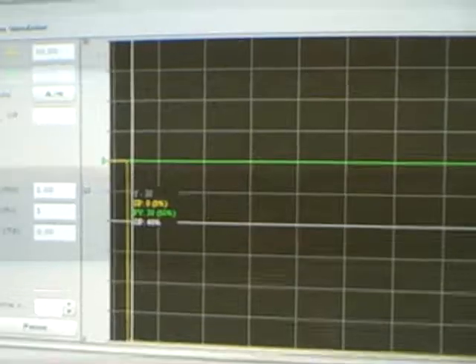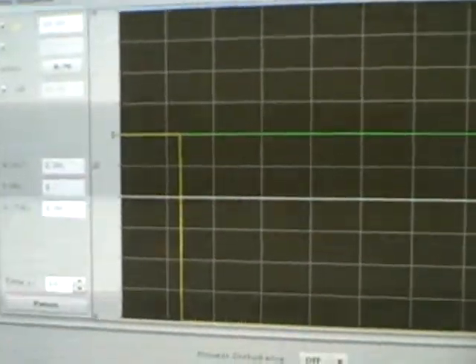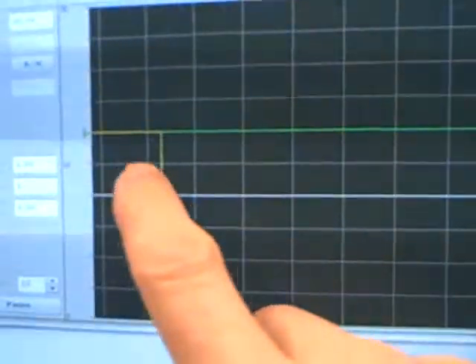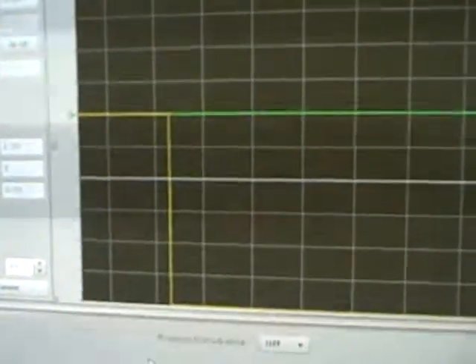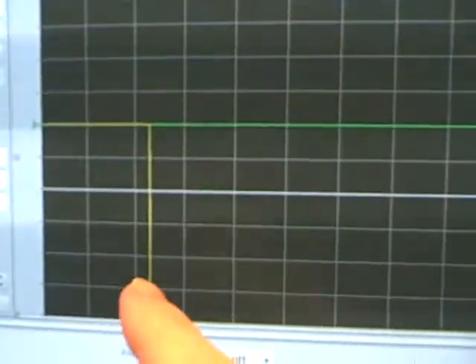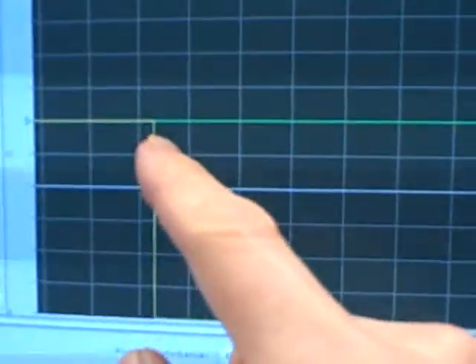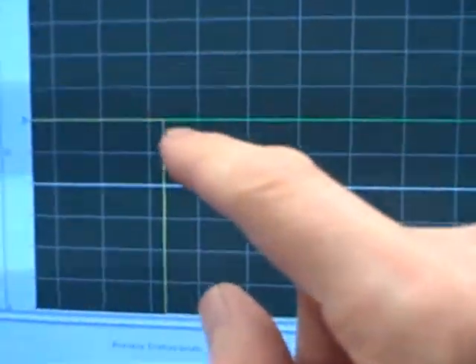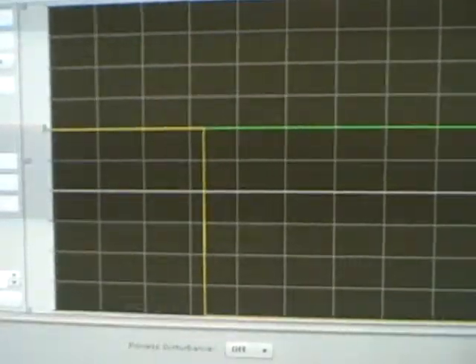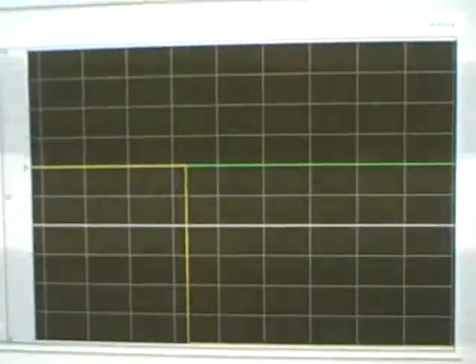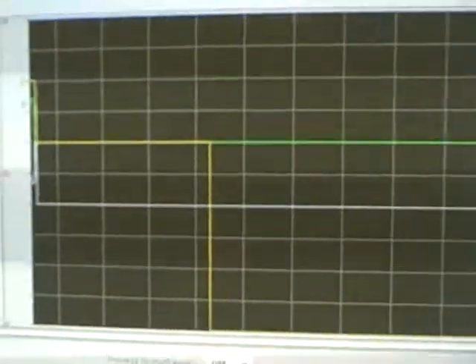I'll switch the controller into automatic mode. Now, the controller is actually going to take action if it sees an error develop between process variable and set point. When I made the change to automatic mode, we see the set point value in yellow jump up right here. Basically, it went through the set point tracking feature. When we came out of manual mode into automatic, it forced the set point to equal the process variable. So right now, PV and set point are equal, zero error, and we're holding in a steady state condition. I'm going to now take my set point and change it to 40% from 30, and we'll see the response.